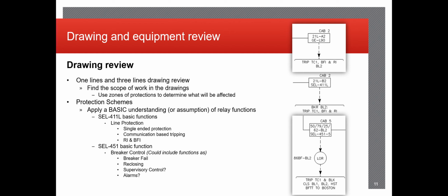The 451 is most commonly used for breaker control specifically. It covers most of the equipment that surrounds a breaker itself, offers some of the same protective functions such as the breaker failure, reclosing, and also offers supervisory control and alarms to SCADA, which could be utilized to let dispatch know, the dispatch on the client's end, that the breaker failed or there was a fault that occurred somewhere in the yard.